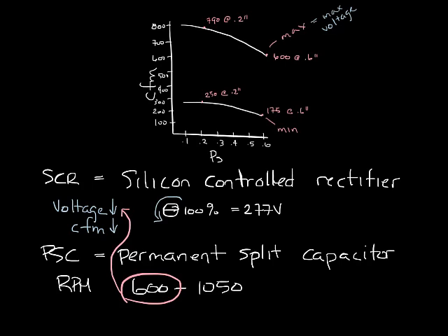The way fan box manufacturers do this is by setting a minimum turn down on the SCR. This is based on the manufacturer's fan box testing to ensure that over normal operation pressures, the SCR keeps within its operating range. So back to the minimum fan curve line. The minimum fan curve represents the airflow when the SCR is at minimum, or the line where you stay above 600 RPM.